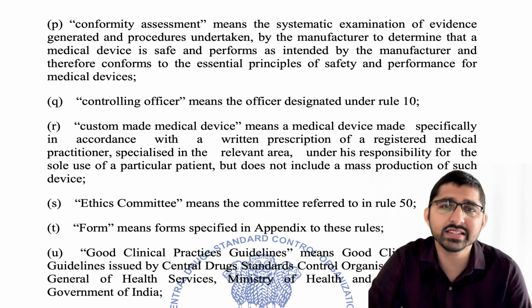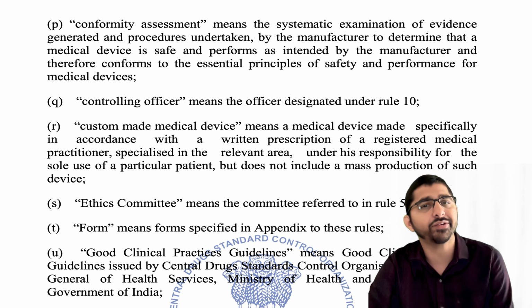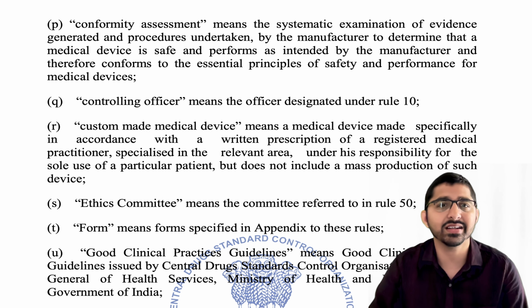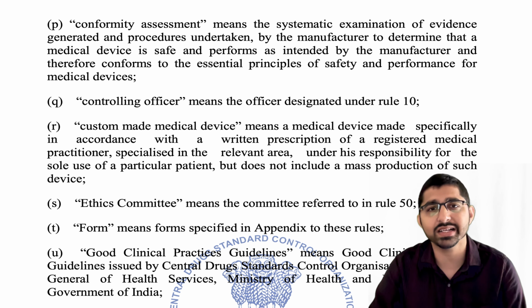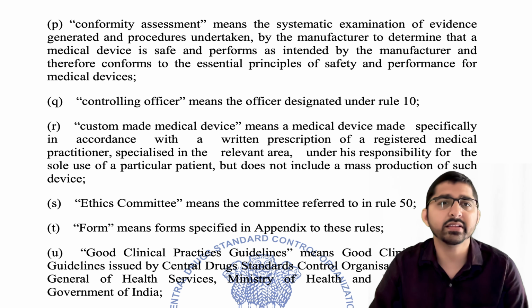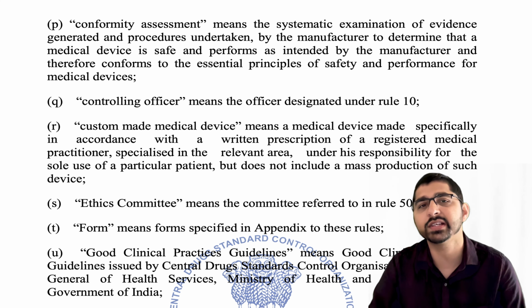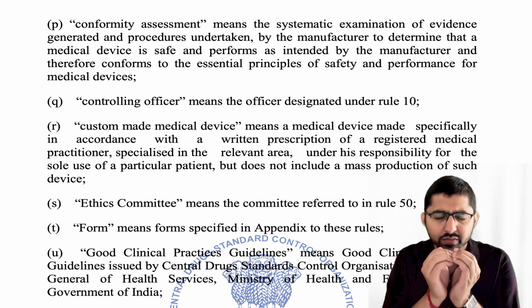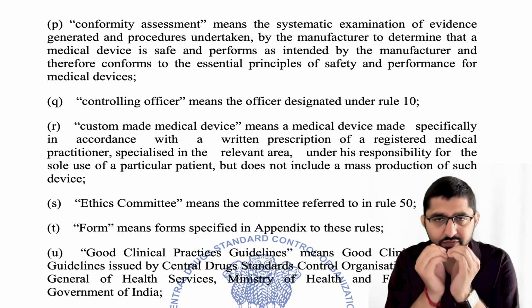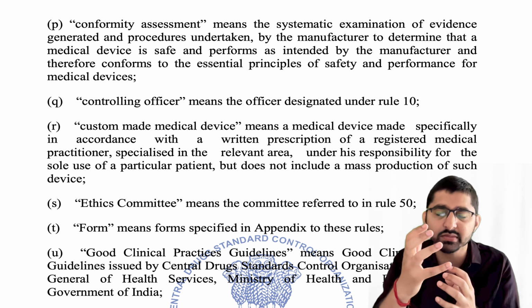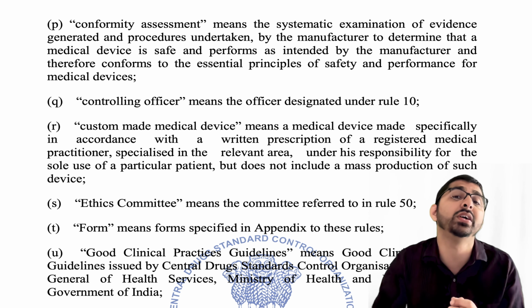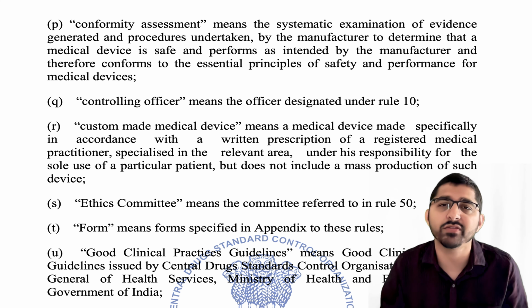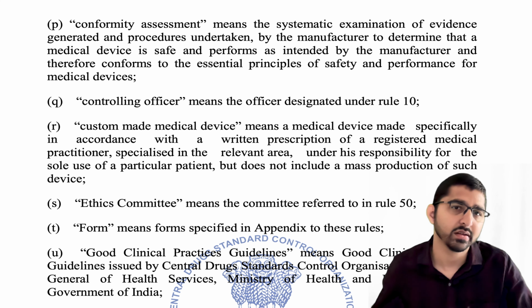Or you can call it the systematic examination of the evidence generated and procedures undertaken by the manufacturer to determine that a medical device is safe and performs as intended by the manufacturer, and therefore conforms to the essential principles of safety and performance for medical devices. So in simple words, whenever we use this word conformity assessment, you need to keep in mind that whatever medical devices or IVD you are going to produce should comply with the essential principles of safety and performance of medical devices, right?